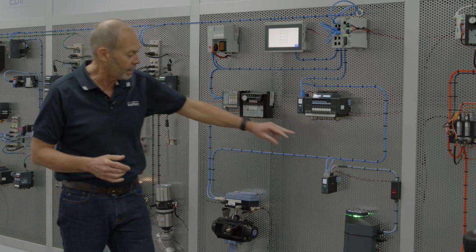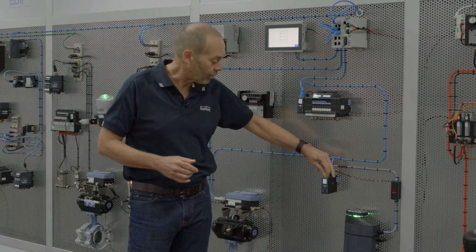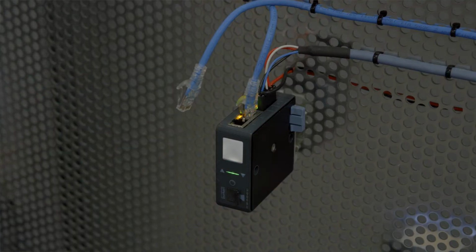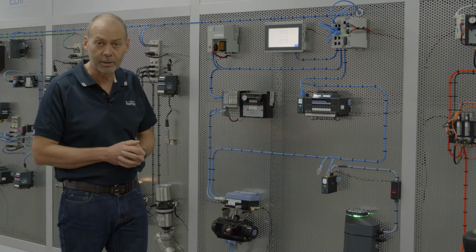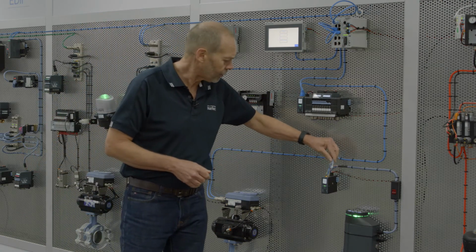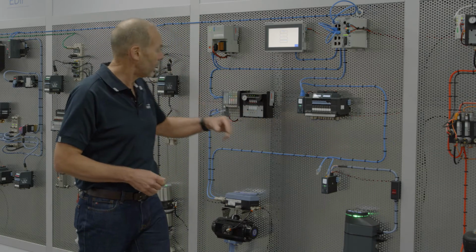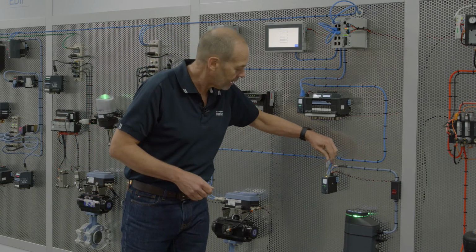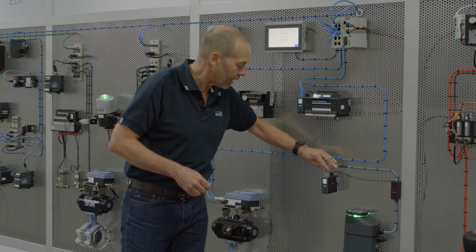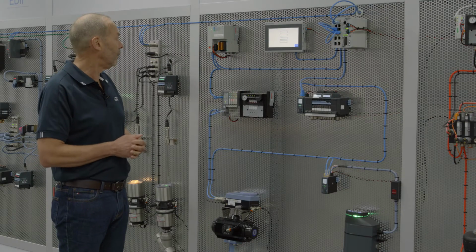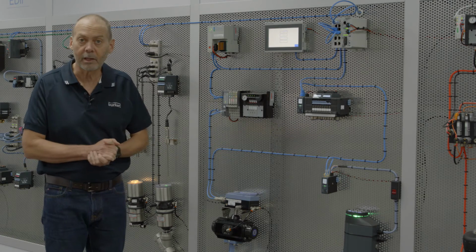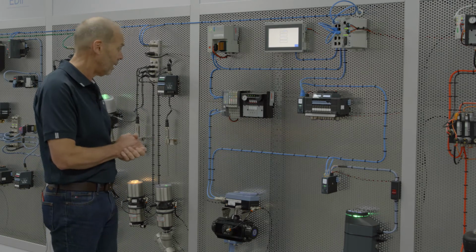What it gives you the ability to do is have a break in the network, which I'll simulate here by disconnecting the unit, and everything stays green and everything stays operational. And of course, it is reported as an error, so that if you're alerted of that break, you can go and repair it. And on plugging it back in again, it immediately corrects itself and goes back to full run mode.